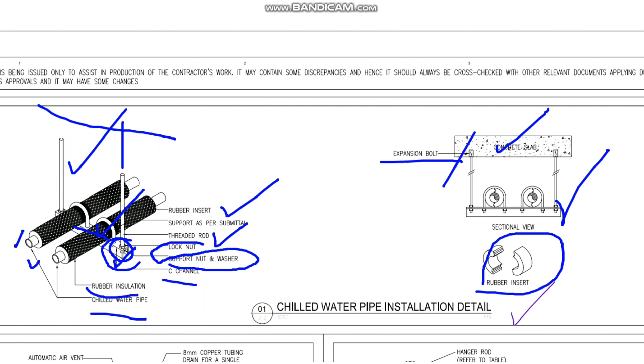Similarly, for the vertical pipeline, you can see this arrangement. This is the RC wall, and this is the vertical pipeline passing in the shaft and other areas. The first arrangement has the expansion bolt connecting with the wall. After that, we have the steel channel, shown here. Then we have the U bolt or band strap, and the rubber insert, which will be installed in between the pipeline.